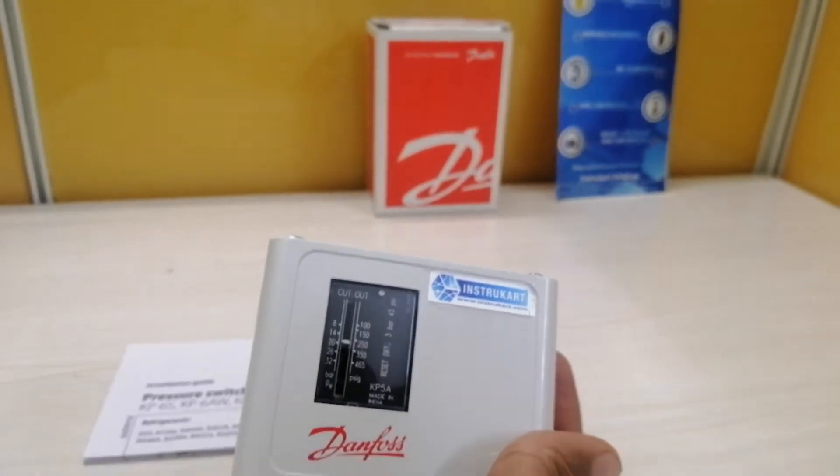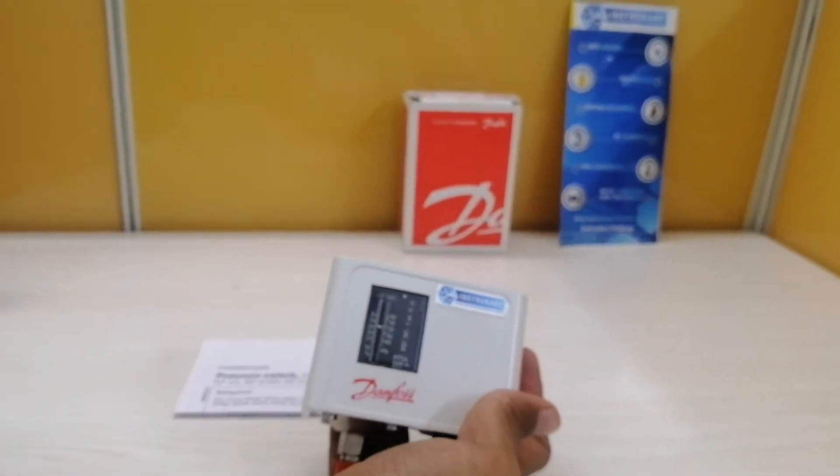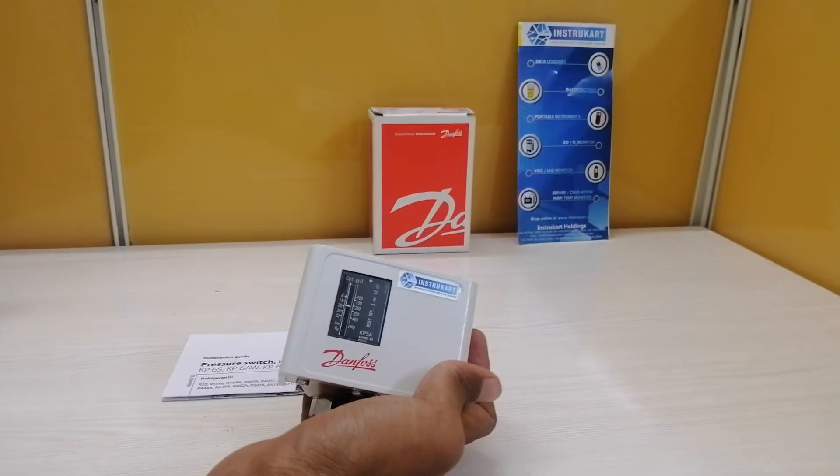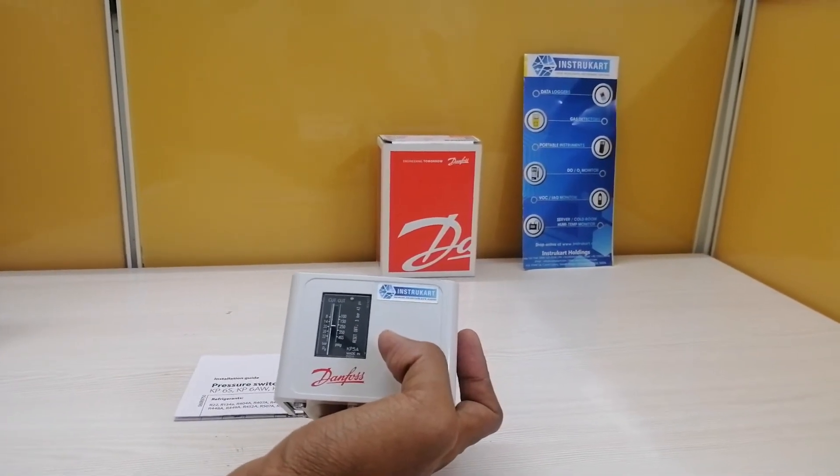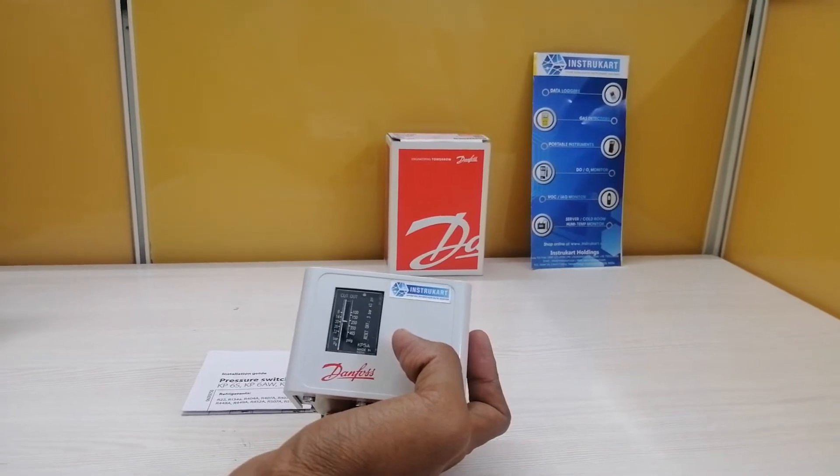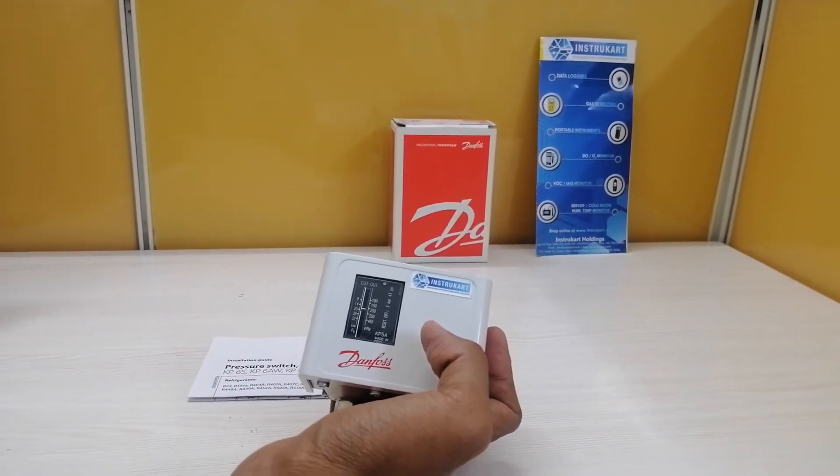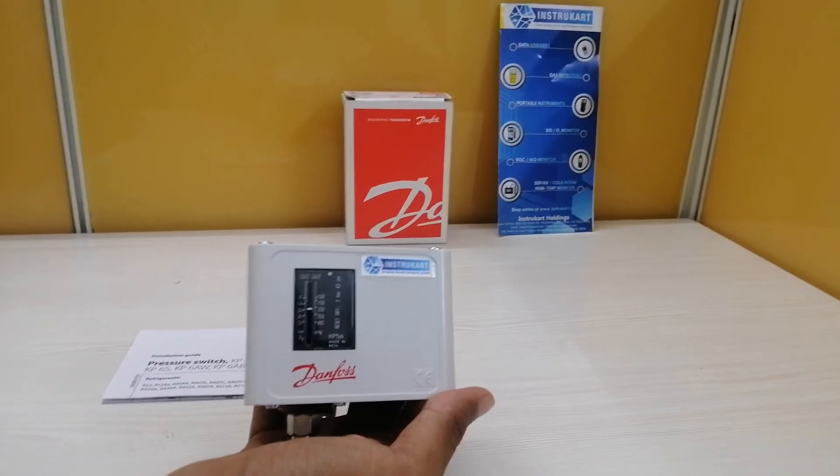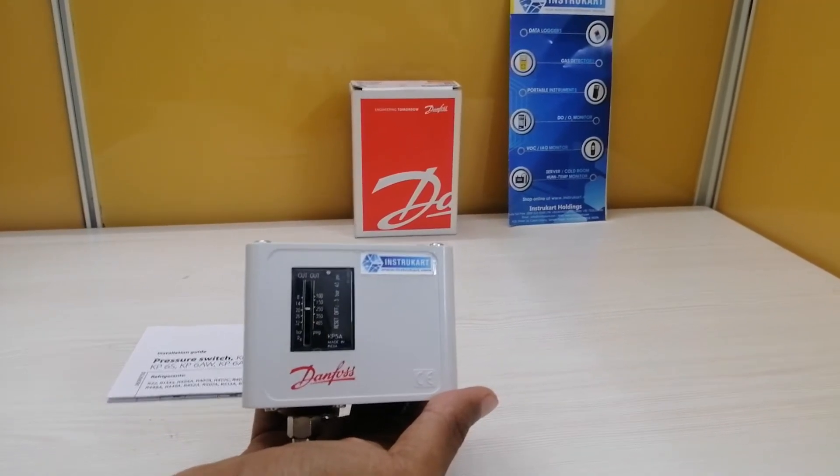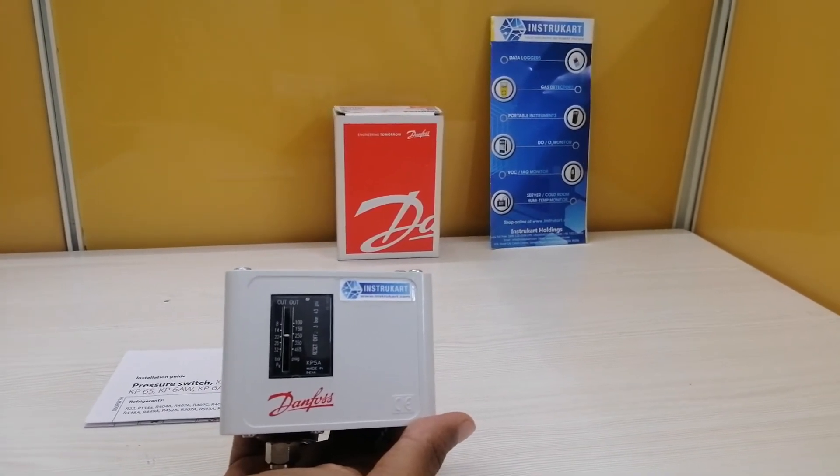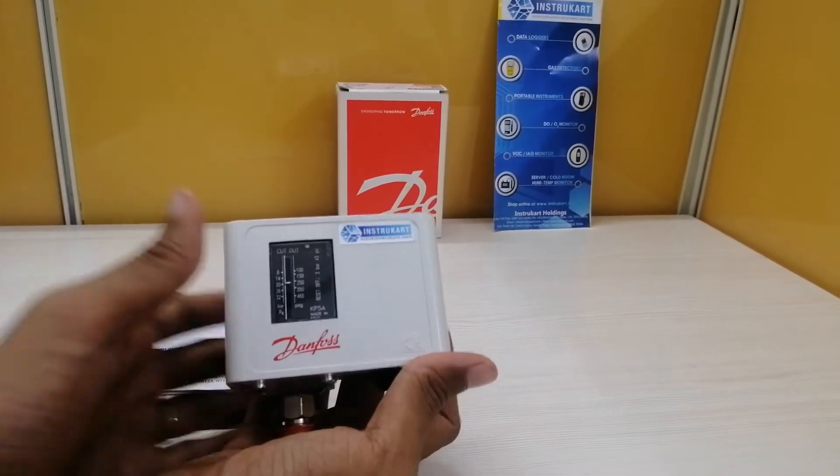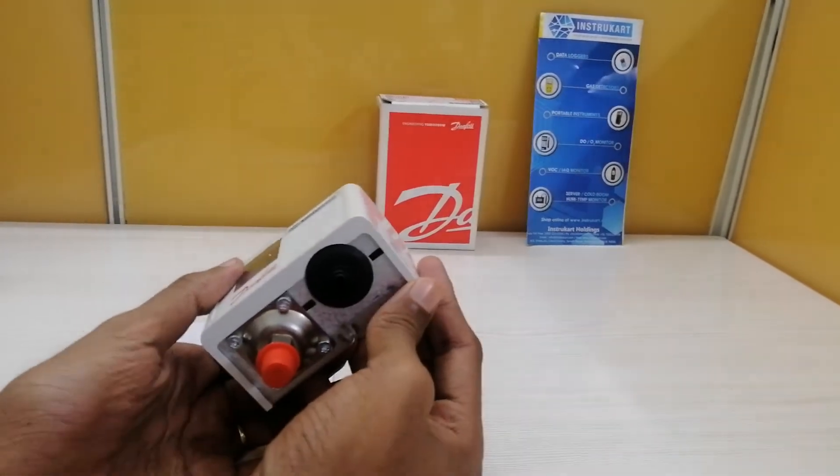Coming on to technical data of this particular instrument, it is having the measuring range from 8 to 32 bar. The differential pressure range is fixed, that is 3 bar fixed. The connection type is SPDT, and the protection class is IP30.